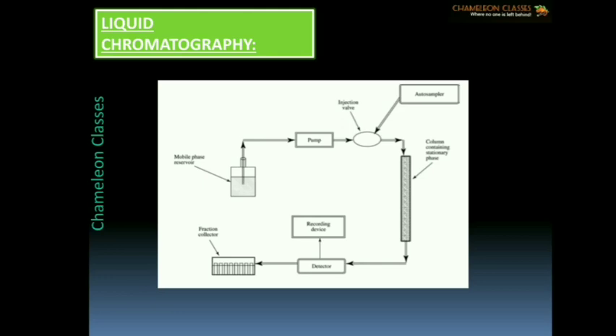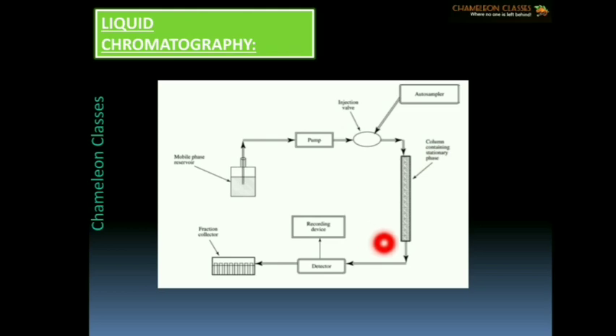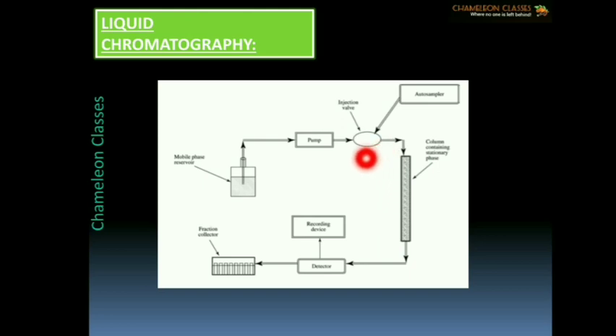As you can see, there is a mobile phase reservoir where the buffer or mobile phase is stored. By the help of a pump, it is injected into the column. There is a sample injection point where the sample can be injected manually or using auto-samplers at a given flow rate. The injection valve helps in convenient sample injection and also helps maintain the gradient of the mobile phase in binary or quaternary systems where more than one mobile phase is used.